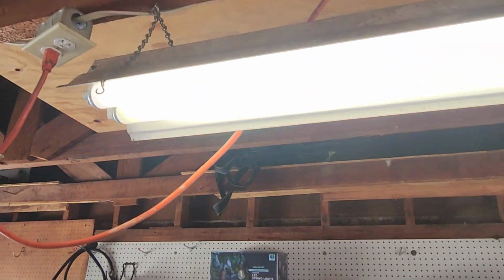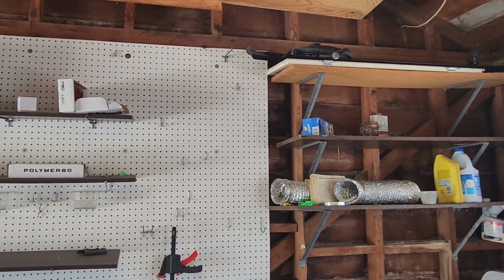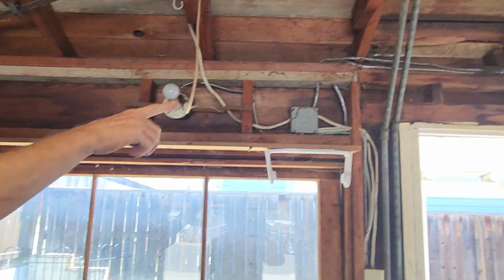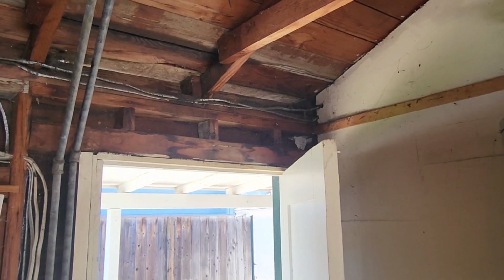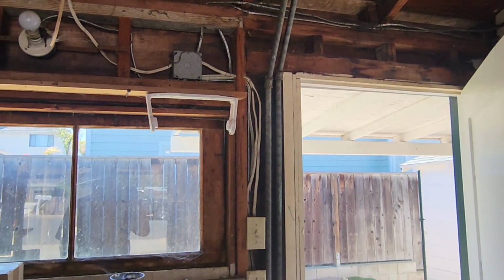So it'll all be in the report. Moisture stains on the walls. And then yeah, that Romex goes right out to the outside. Yeah, well, and there's a comment saying you've got electrical cable passing through the wall there and here, but you know, by today's standards, it should have conduit when it goes through the wall. Right. It should be in like a conduit.